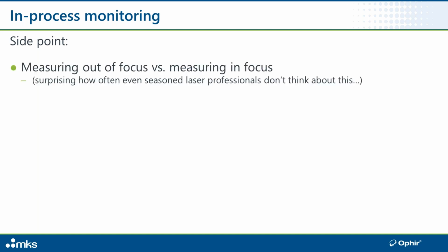It's the same number of watts in focus as out of focus, just not the same number of watts per square centimeter. So you want to find a location where the beam is defocused and do the measuring there. And you want to make sure that there is somewhere where the power density is safely below the limits that are specified in the sensor's data sheet.